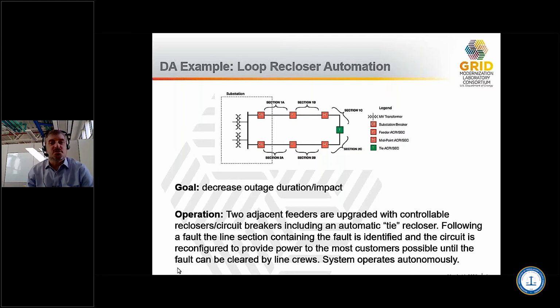But then it actually restores the customers that it can via a different path. So for instance, if that fault happens in section 2A, the circuit breaker there in the lower left would operate, as would the red box to the right. And then what eventually would happen is that this equipment is automated, so it's communicating amongst itself and figuring out, okay, how do I bring the most number of customers back on? The idea would be that after a short outage, the tiebreaker would close and would effectively bring that section 2B and 2C back online, right, via the other feeder. So it's really an automatic reconfiguration type scheme meant to, again, reduce customer outage and that sort of stuff.